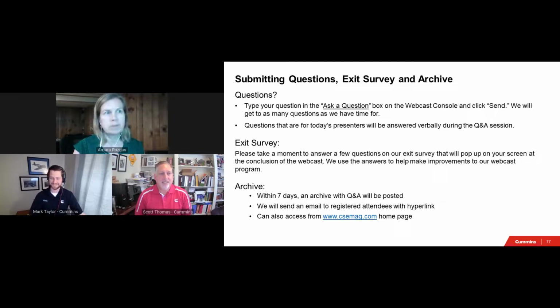Awesome. That's a really cool question because it kind of reminds me of hypermilers, people who are trying to run as effectively or as efficiently as possible. I would say, first off, the most important thing to mention is the rating of a generator set. Let's call it a 1 megawatt, 1,000 kilowatt product. Generally speaking, the sizing of a product to accommodate cyclical loads, to accommodate motor starting, that's part of the reason why there's a general recommendation that you size a product so that 70 to 80% of the nameplate rating is where you're generally at for your loads, just to accommodate the cycles and as things come and go. You need a little bit of breathing room on that engine and that generator set.